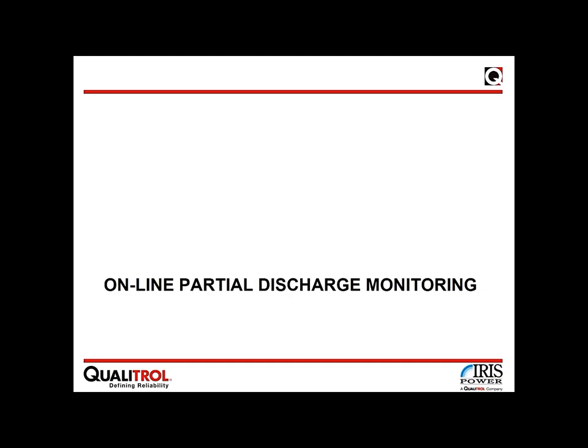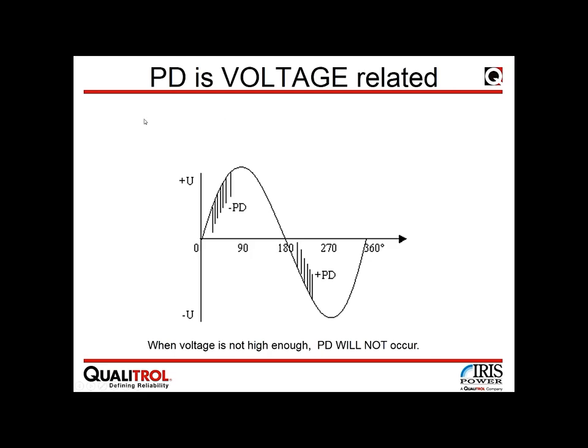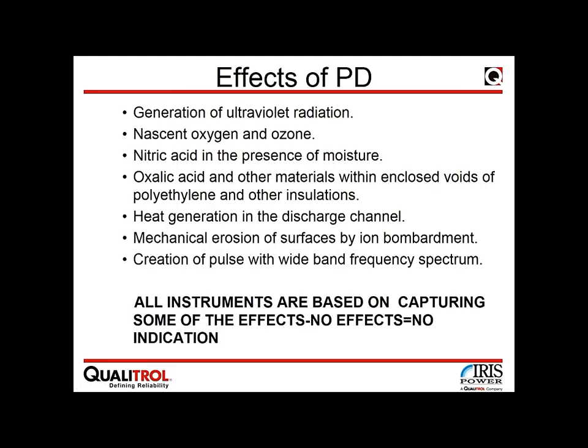The first technology is online partial discharge monitoring. Partial discharge is a process taking place in or on the insulation of the stator winding, occurring because the winding is not perfect and allows internal discharges and surface discharges between different phases. Partial discharge is a voltage-related phenomenon — if voltage is not high enough, it will not occur. It only happens in parts of the stator winding exposed to sufficiently high voltage and suffering from production or operational defects.